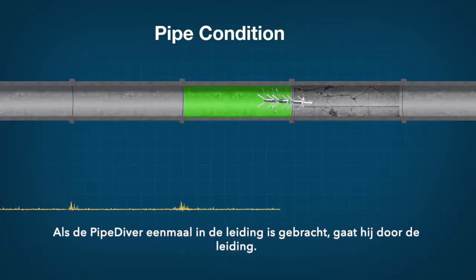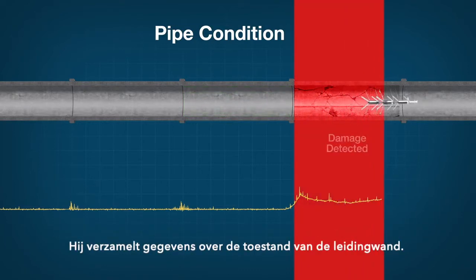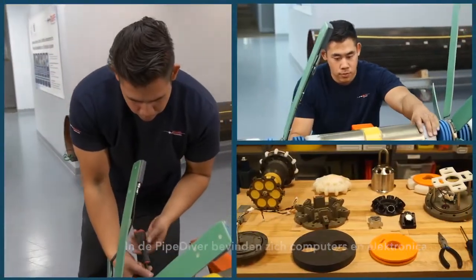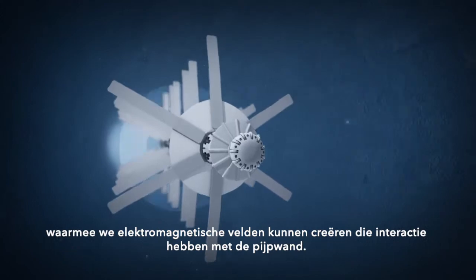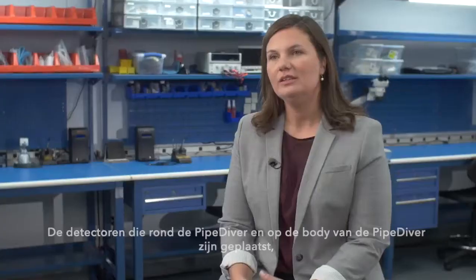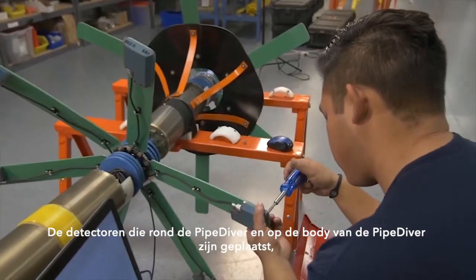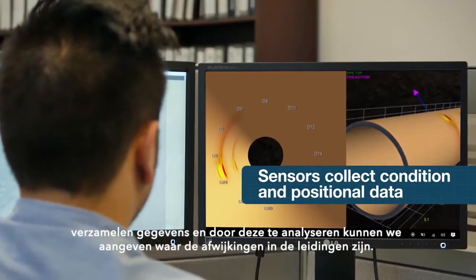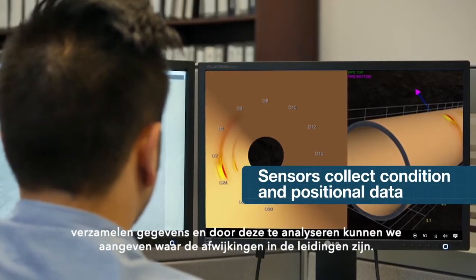Once it's been inserted into the pipeline, it travels through the pipe, collecting data about the condition of the pipe wall. On board the Pipediver there are computers and electronics that allow us to create an electromagnetic field that interacts with the pipe wall. The detectors positioned around the Pipediver petals and on the body of the Pipediver collect that data, and we're able to analyze it and understand where the problems in the pipe wall are.